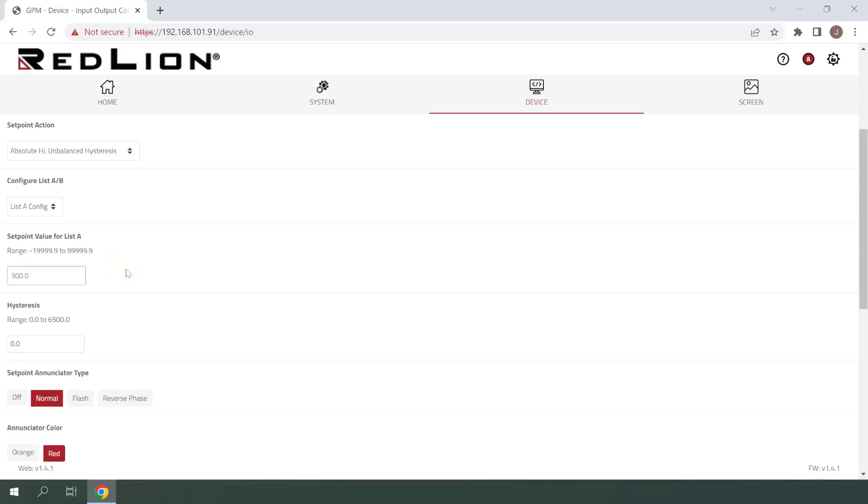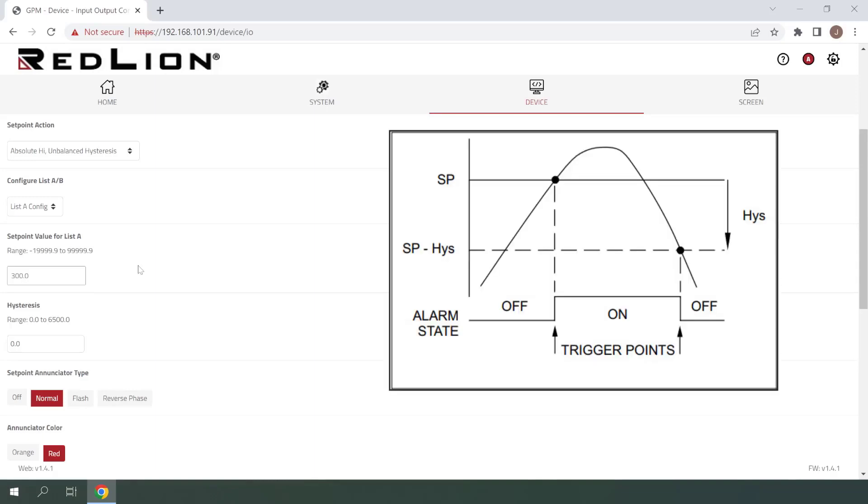The next setting we see here is Hysteresis. I'll put a value of 50 in here for the example, and with unbalanced Hysteresis, this means that if our measured value were to rise above 300, the setpoint alarm would trigger and stay active until the measured value falls to 250.